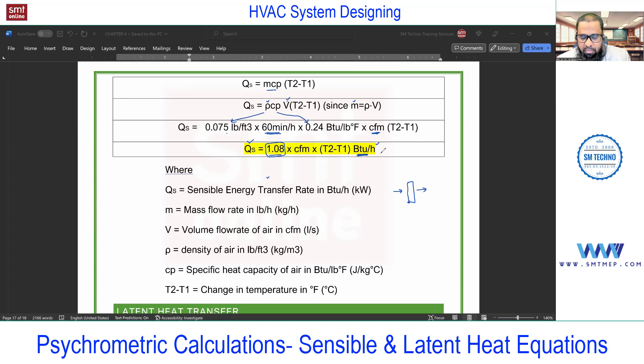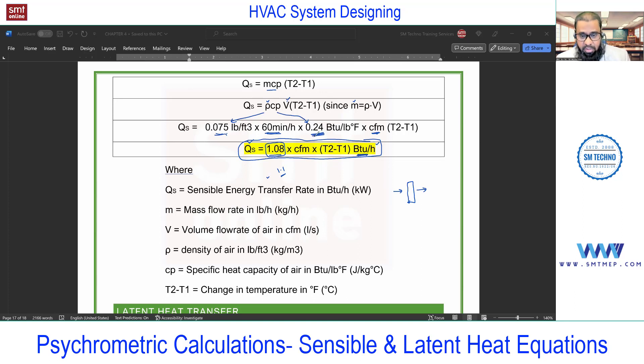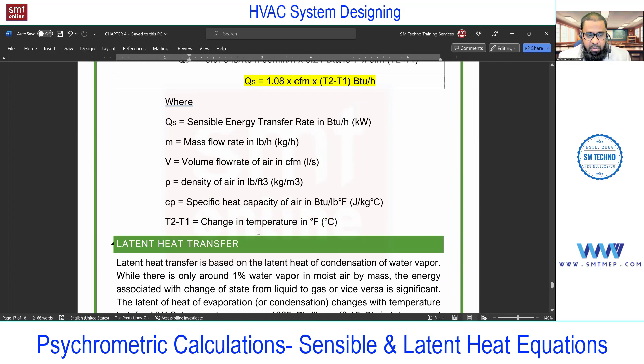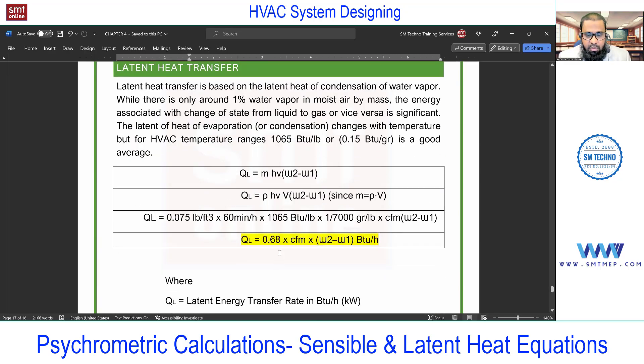In some books you may find 1.1 instead of 1.08, because the density and specific heat values may vary slightly by standard. In the Carrier handbook you'll find 1.08, and in the ASHRAE handbook you may find 1.1. The difference is only 0.02, so you can ignore it — don't get confused between 1.08 and 1.1. Now, similarly, for the latent heat equation, how do we get 0.68?